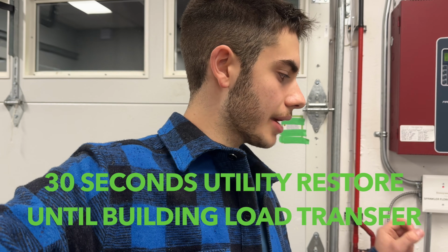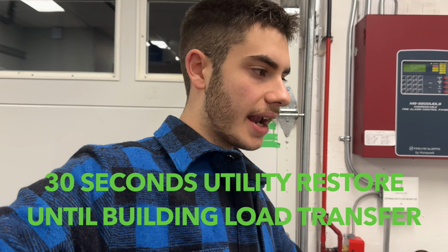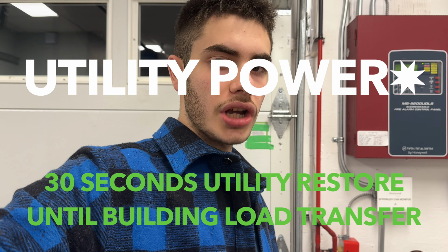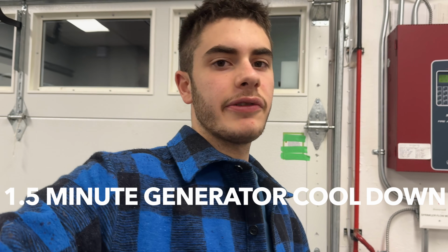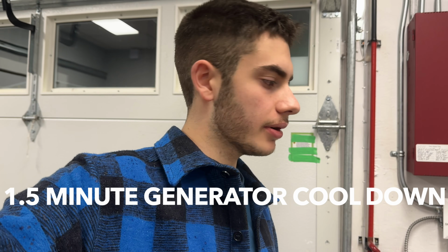And then on the other side of things, once utility power is restored, the transfer switch will wait 30 seconds before transferring back to utility power. And then the generator, from when utility power is restored, will wait 1.5 minutes before shutting down to give it a bit of a cool down period. And the 30 seconds before transferring is just to make sure power is good and stable before transferring back to that utility power.